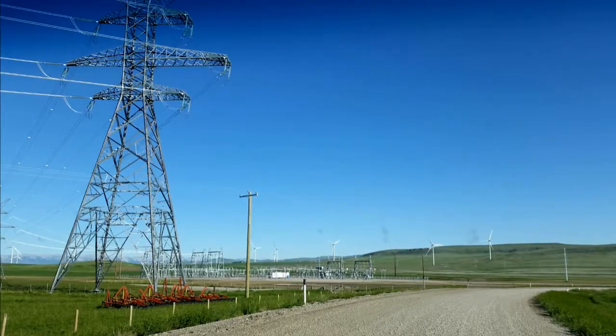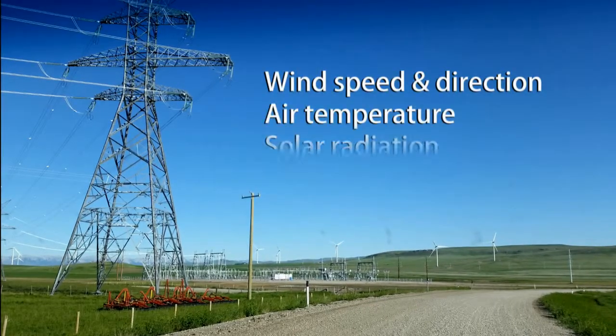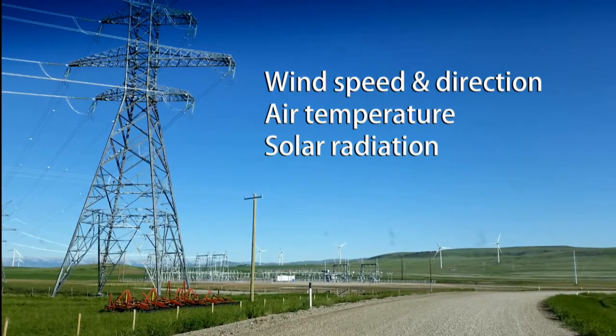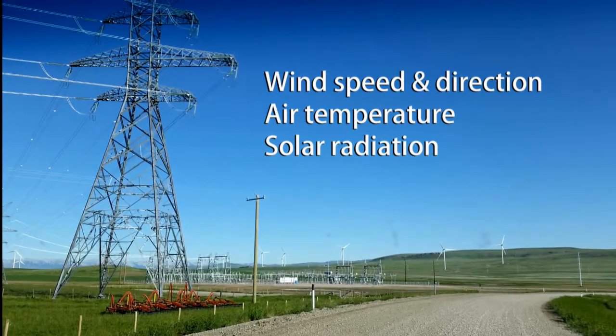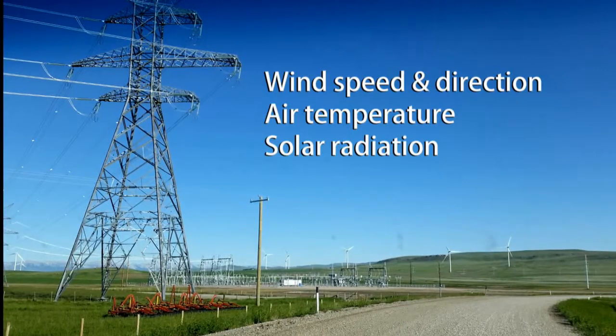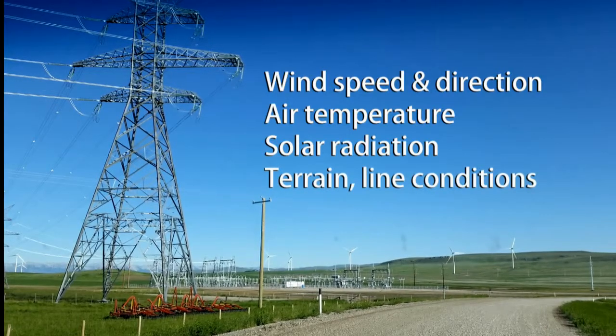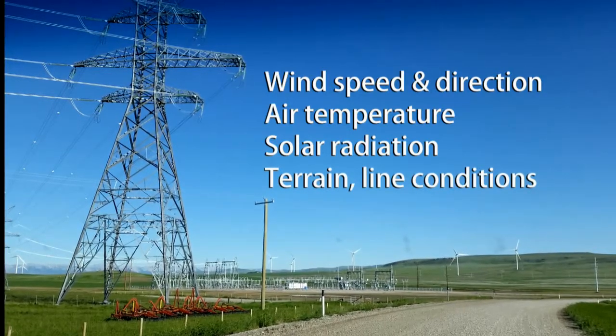It accounts for dynamics such as wind speed and direction, ambient air temperature, and solar radiation exposure, all of which affect the relationship between current and temperature. It also factors in variables such as terrain.